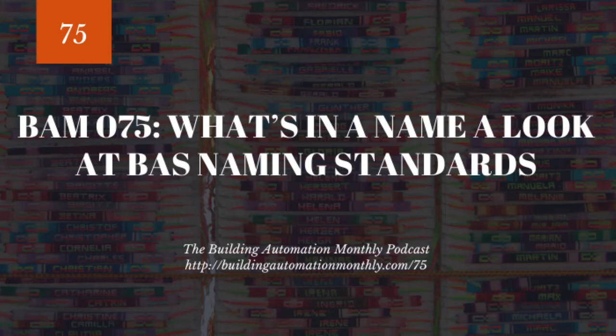So you go, all graphics or all names or all points shall be consistent with naming or point or graphic standard X, and that standard can be found in attachment A, BAS standards. And that would be your specification language. And then you would attach attachment A, which would be your BAS standards. And there's slews of BAS standards out there, and you can pick any which way you want to go. On the high end of things, you've got folks like Penn State, which have really complex standards. And then you could just simply have something that is much easier.